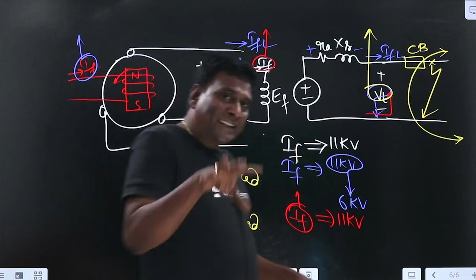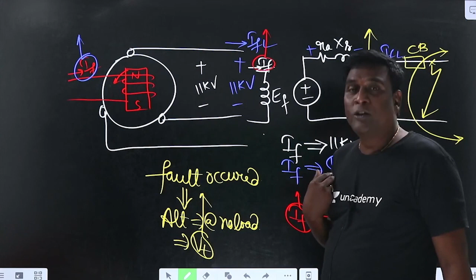So voltage regulation should be defined for alternator or power transformer this way. Because for power transformer or alternator, my terminal voltage is going to be constant, independent of loading conditions. Because in power transformer we have taps, and for alternator we have field current. So by varying taps in power transformer or by varying field current in alternator, we are going to maintain terminal voltage the same. Now terminal voltage is going to be the same, but why should I calculate voltage regulation? Yes, in order to design the insulation, first thing.